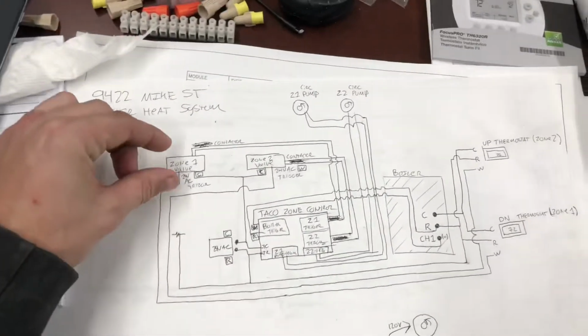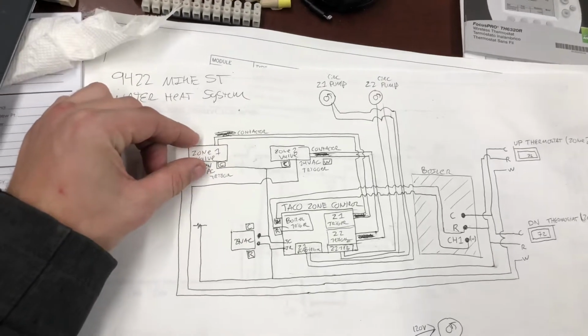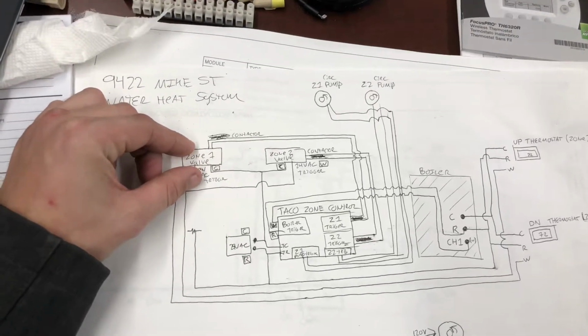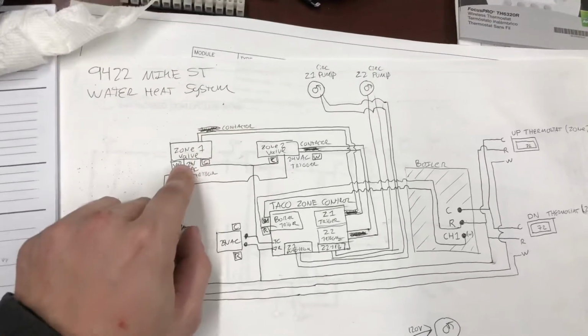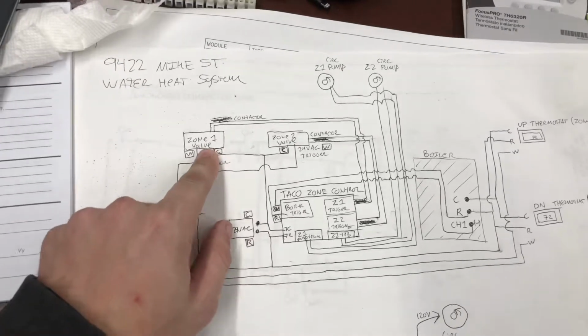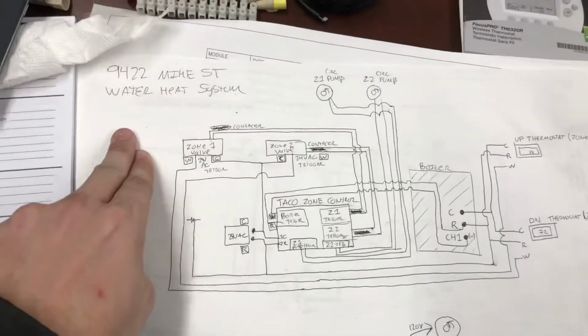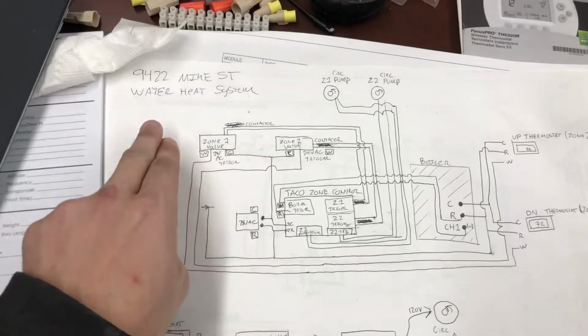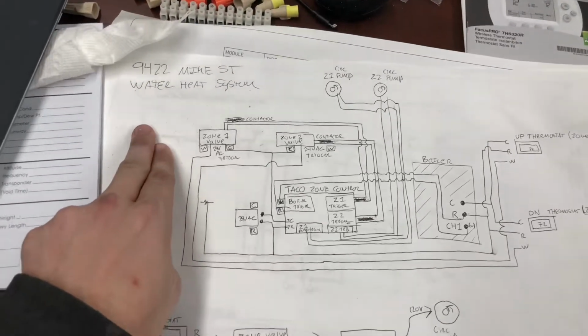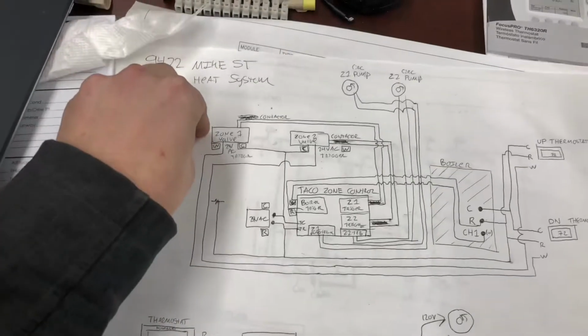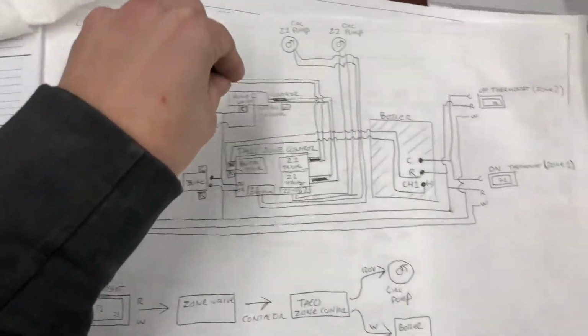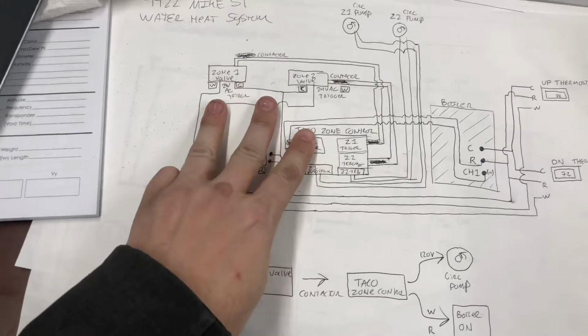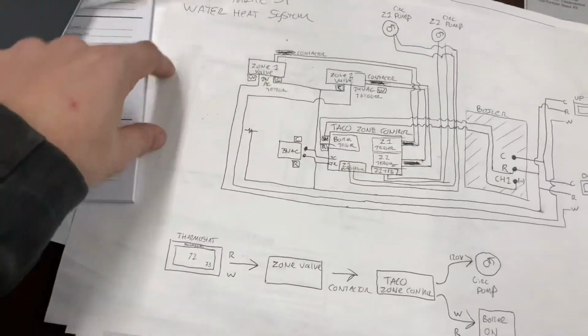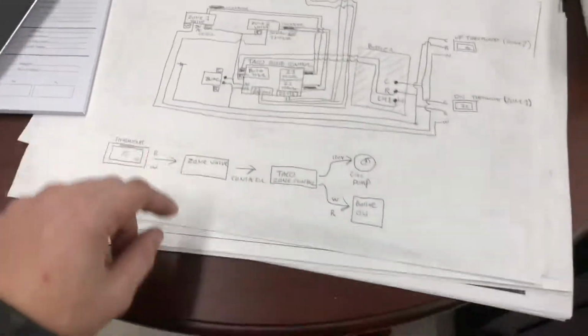So if you had all of your house zone valves and pumps on one zone, you could just wire it all like this. So have both main floor circulation pumps and both main floor circ valves all kind of paralleled together on one zone in the taco. Then you had your garage on the other. You could do it that way. Otherwise, if you have a 3-zone taco, you could just get another zone valve and wire the circ pump differently.